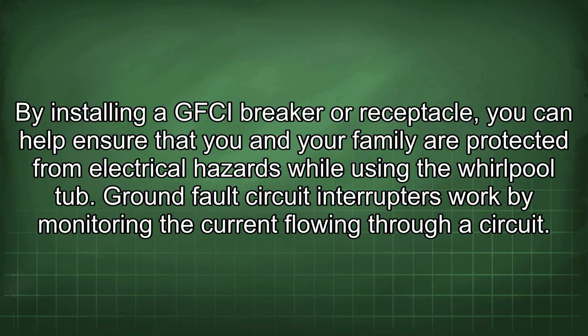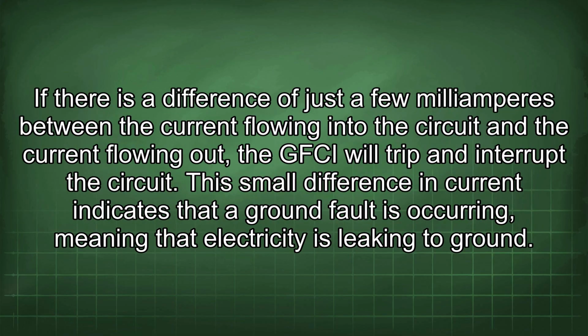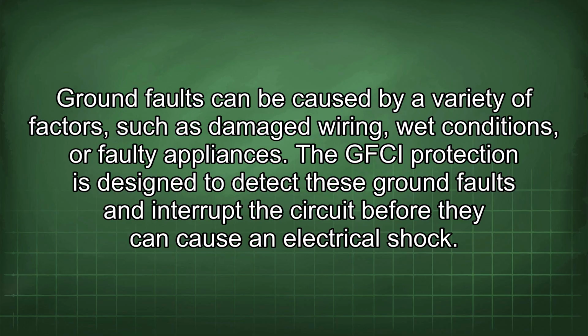Ground fault circuit interrupters work by monitoring the current flowing through a circuit. If there is a difference of just a few milliamperes between the current flowing into the circuit and the current flowing out, the GFCI will trip and interrupt the circuit. This small difference in current indicates that a ground fault is occurring, meaning that electricity is leaking to ground. Ground faults can be caused by a variety of factors, such as damaged wiring, wet conditions, or faulty appliances.